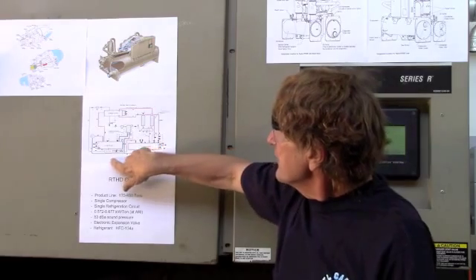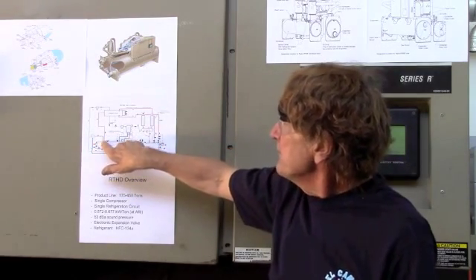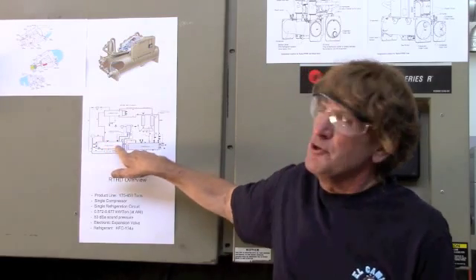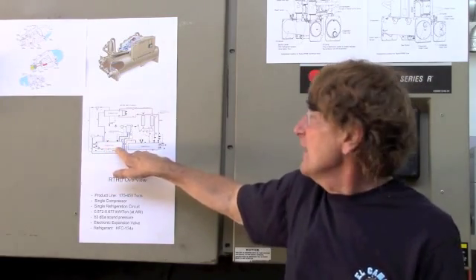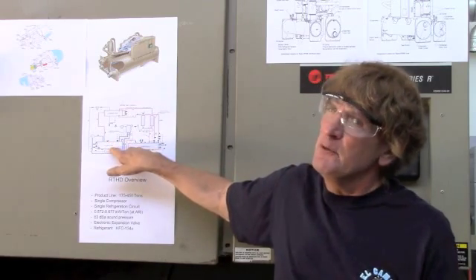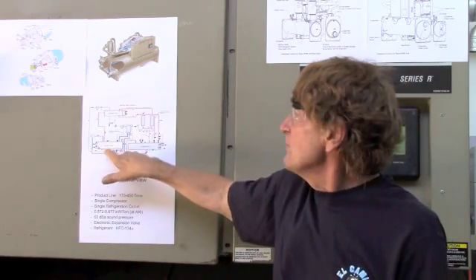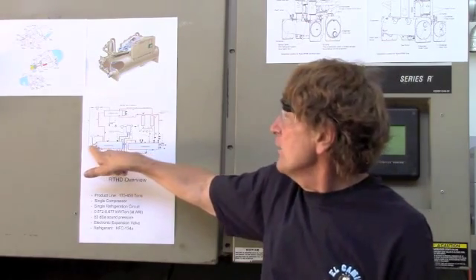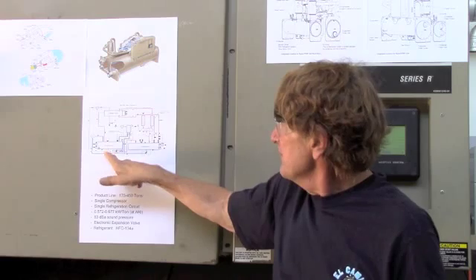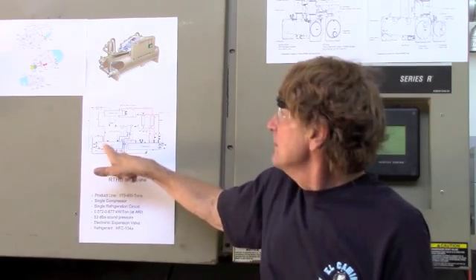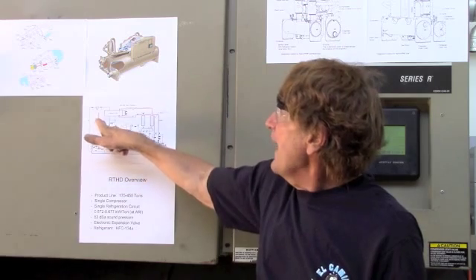It's going to come out of the condenser into the top of the evaporator through an EXV. This is going to be a falling film evaporator. We'll talk about that later. The refrigerant is going to fall down in a falling film onto the tubes, absorb heat from the water that's going out to the facility air handlers. That gas is going to come back, that is now vaporized, back into the compressor.